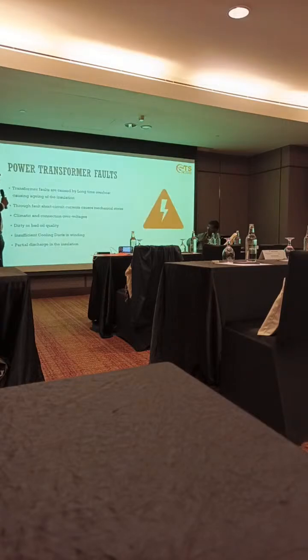Also, in some transformers there will be oil seepage. The oil seepage may lead to a reduction in the oil level. Oil is basically used as a coolant of a transformer. If the oil level goes down, it leads to an increase in temperature of the windings, or if enough cooling medium is not there, it leads to overheating of windings and cores. So it leads to the failure of a transformer.